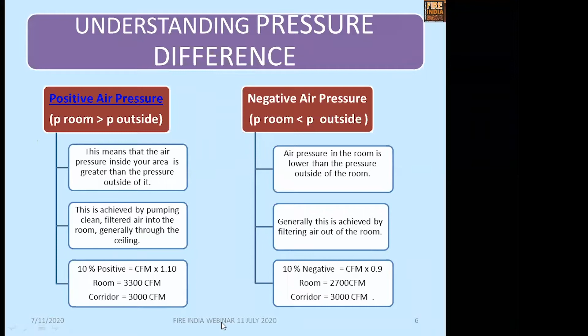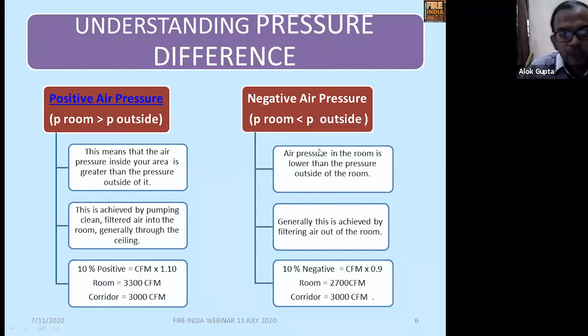So in this case, if the room CFM is 3,300 and the corridor CFM is around 3,000, then the room is said to be positive, and the other side is said to be negative. There are applications, for example, a kitchen exhaust application. This is all the beauty of HVAC and electrical engineers. They calculate different areas and keep them at positive and negative pressure based on building requirements.